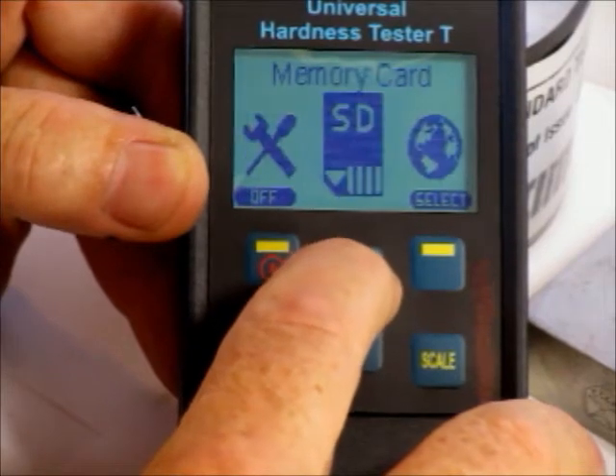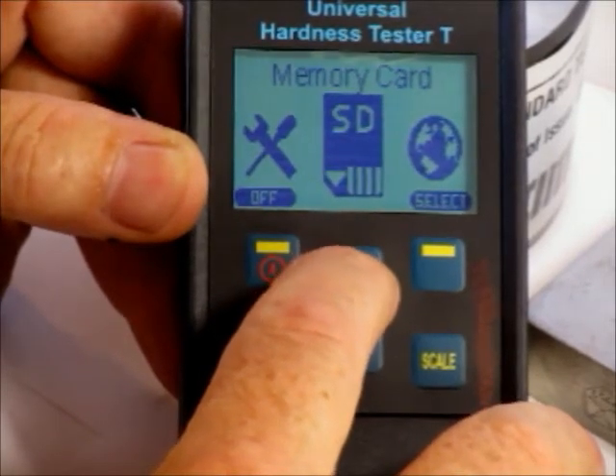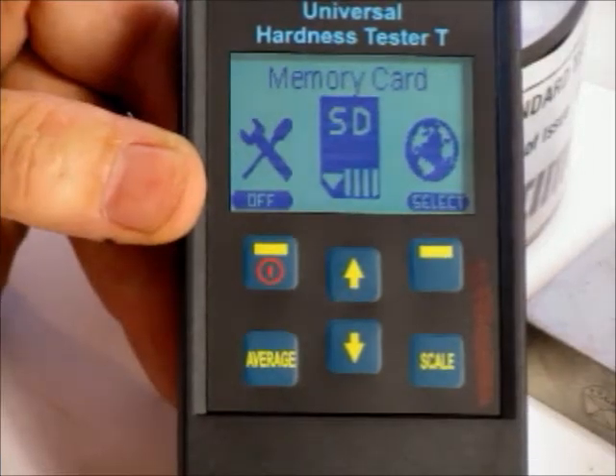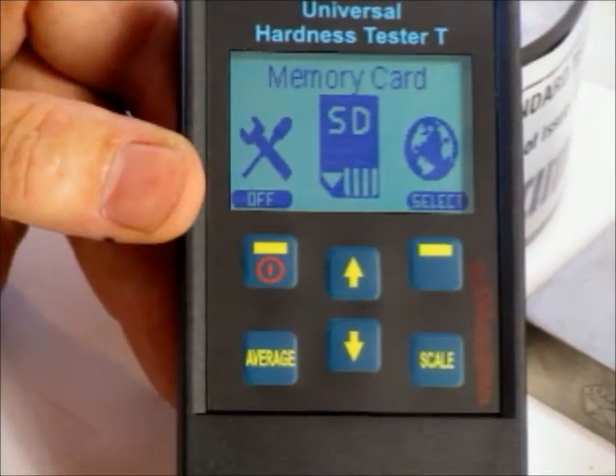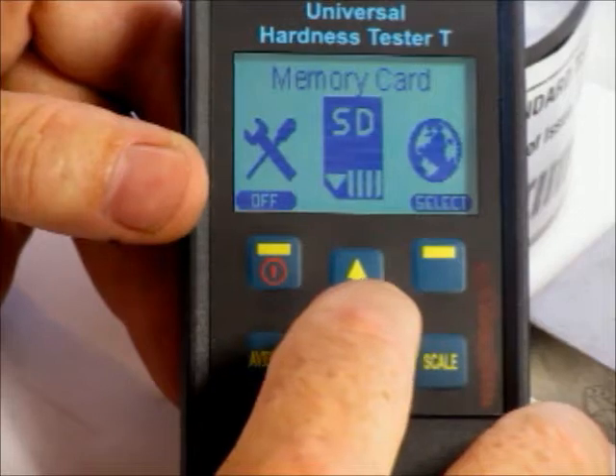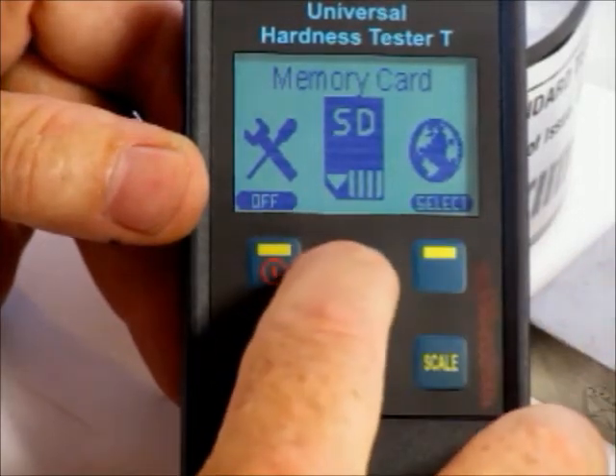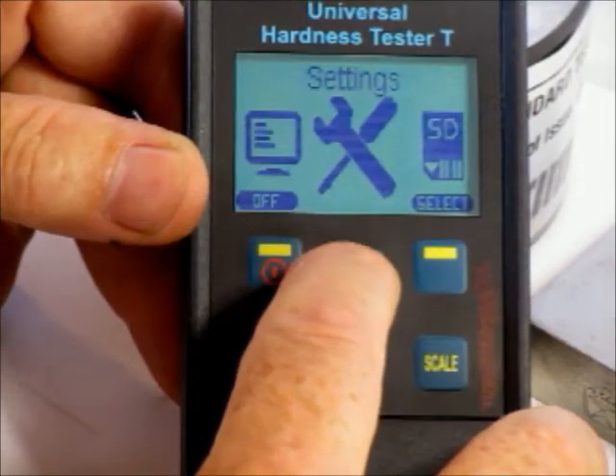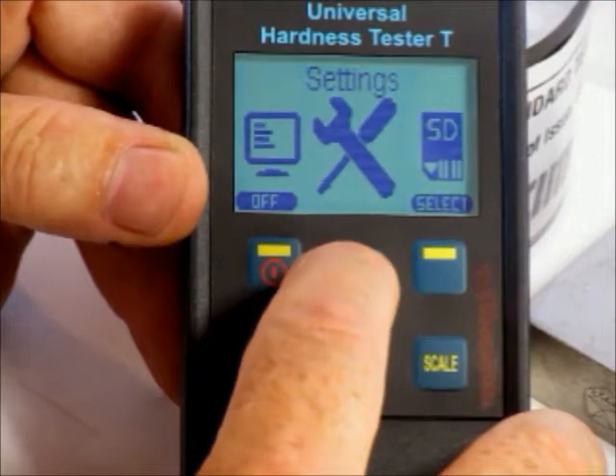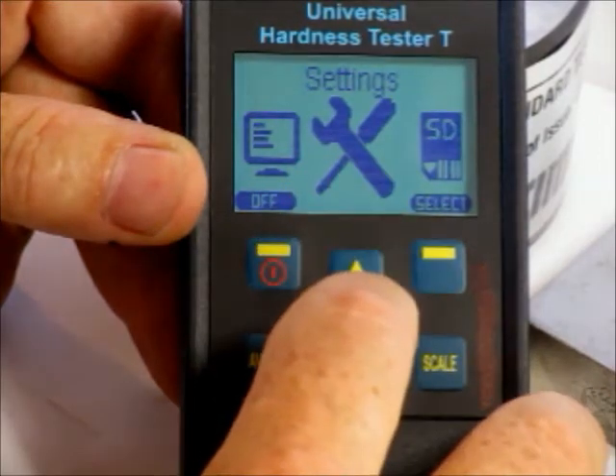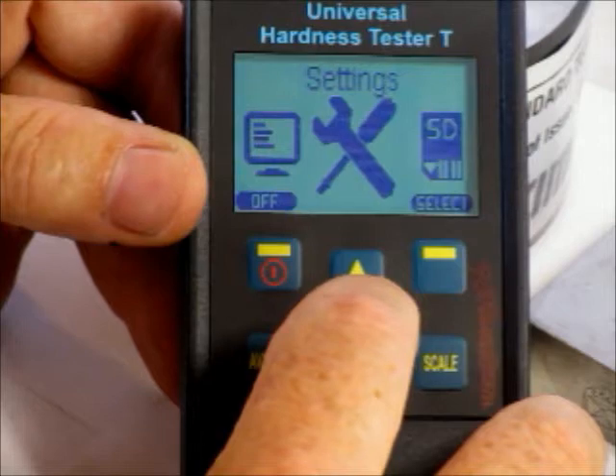If I scroll on further, the memory card, and in the test probe there is a memory card because we actually store the calibrations in the probe, meaning that probes are interchangeable with the tester, kind of unique and very special. Settings for the probe itself and for the display, so we can have it so that we can have a power off value and so on.